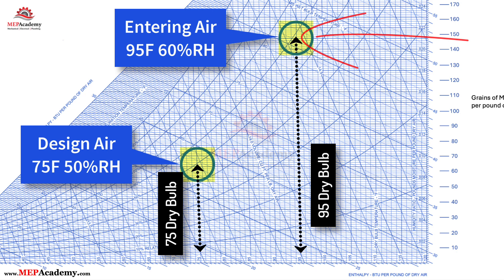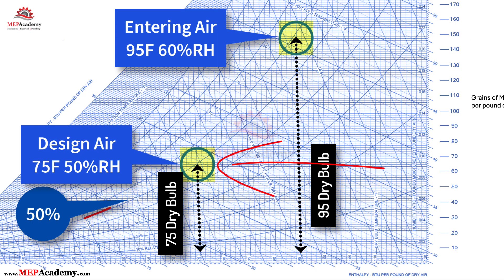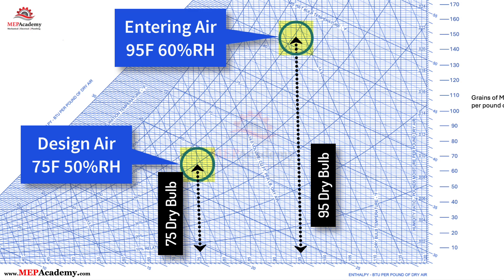Step 2: Plot the desired indoor air of 75 degrees Fahrenheit dry bulb and 50% relative humidity. This is your target condition, comfortable for most people. Step 3: Draw a straight line between these points. This represents the path air must take through cooling and dehumidification.